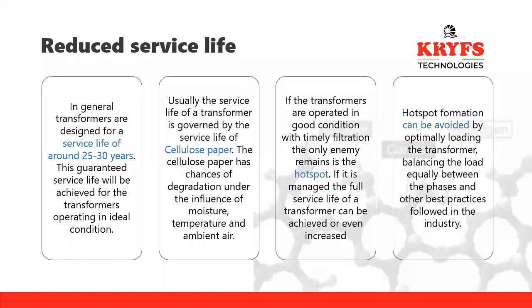Usually the service life of the transformer is governed by the service life of the cellulose paper. The cellulose paper can degrade under the influence of moisture, temperature and ambient air. If the transformers are operated in good condition with timely filtration, the only enemy that remains is the hotspot. If it is managed, the full service life of a transformer can be achieved or even increased. Hotspot formation can be avoided by optimally loading the transformer, balancing the load, especially between the phases, and other best practices followed in the industry.